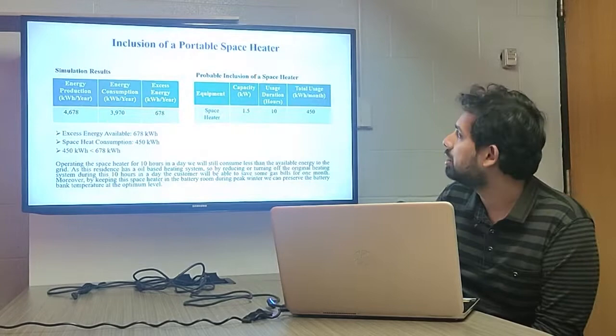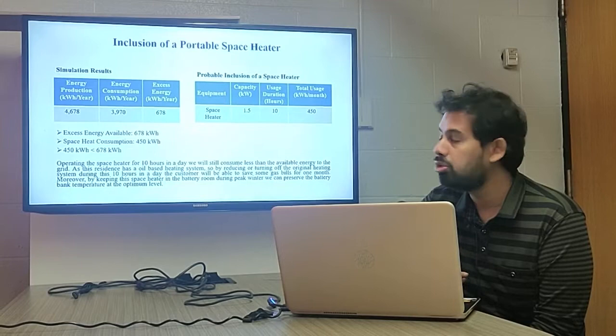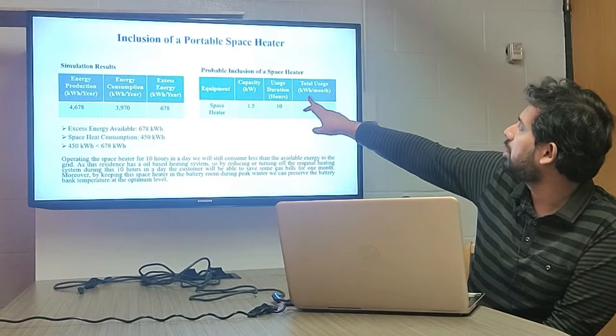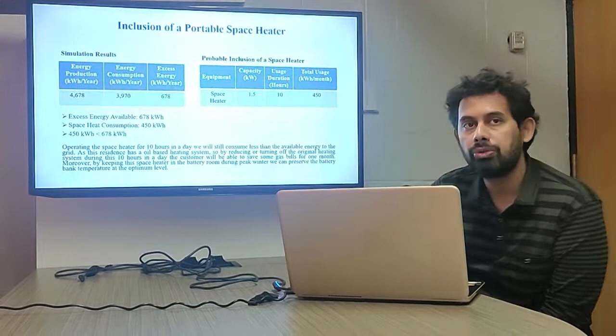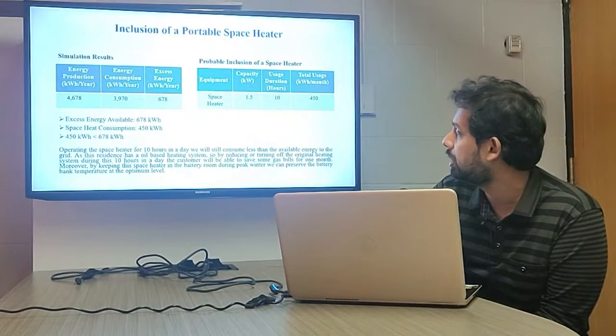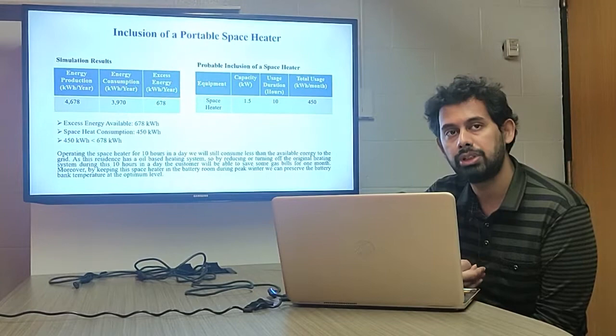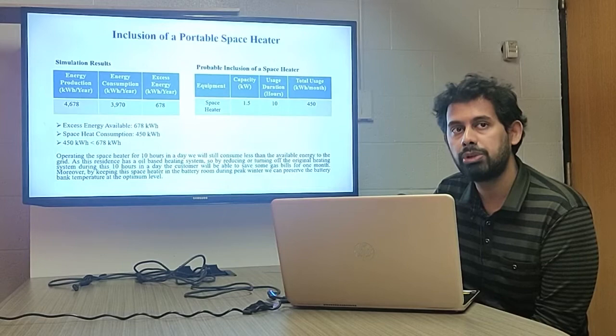The capacity of the space heater is 1.5 kilowatts and it can be purchased from any local market for $150 to $200, so it will not add too much cost. If we operate the space heater 10 hours a day, the total usage will be 450 kilowatt-hours per month, which is still less than 678 kilowatt-hours. By running the space heater and reducing or turning off the original heating system for 10 hours a day, the customer can save on gas bills in addition to already saving on electric bills, making the project far more feasible.